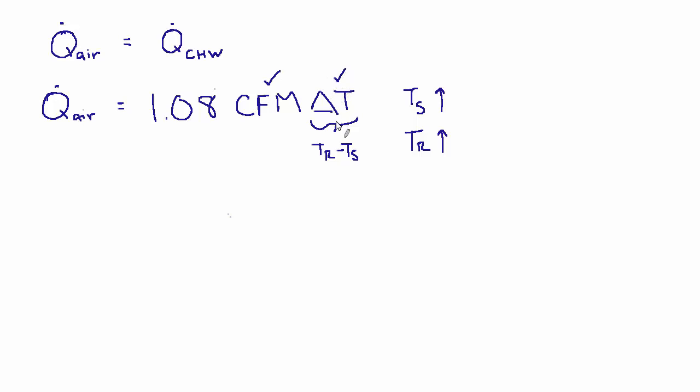Now that may not be precisely true. The return temperature may not go up quite as much as the supply temperature did. So if this goes up one degree, this might not go up one full degree. And in that case, delta T is slightly smaller, and the CFM will have to increase slightly to meet the same heat load. So in that case, there would be an increase in fan energy.